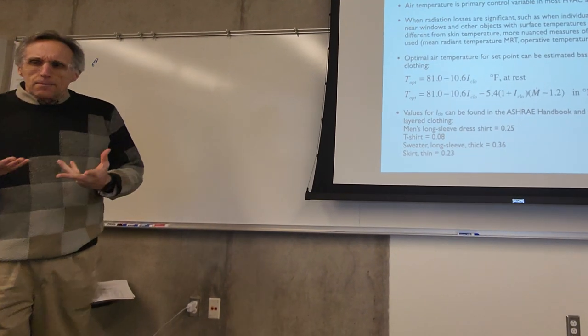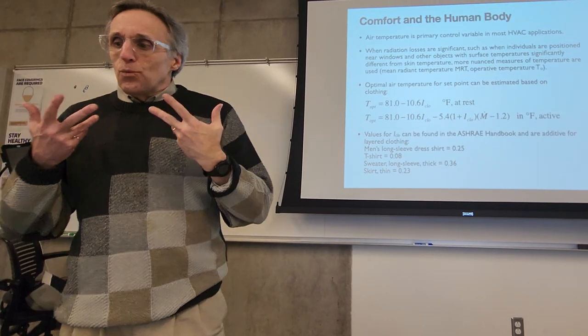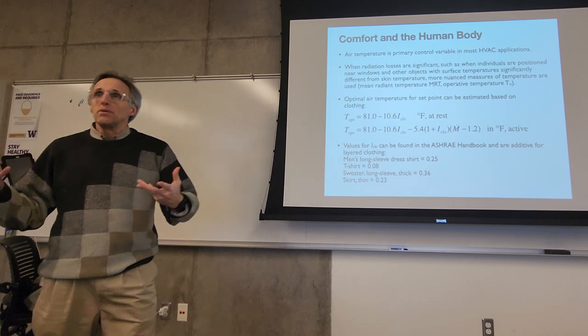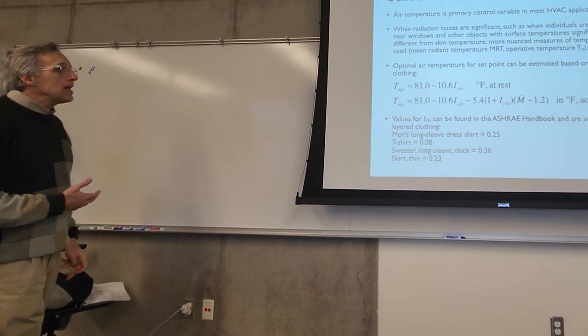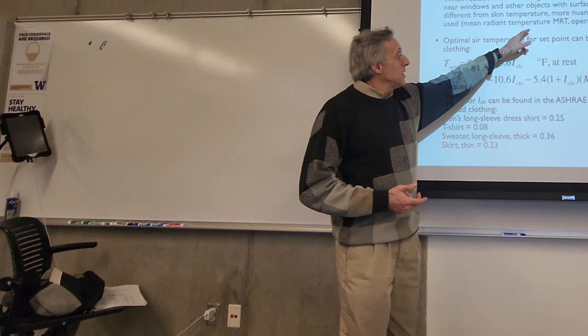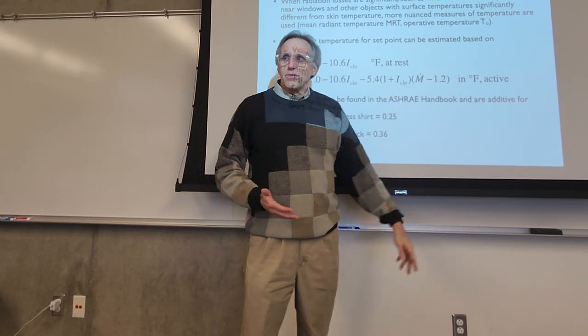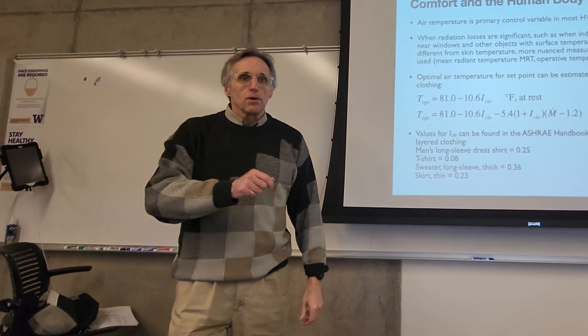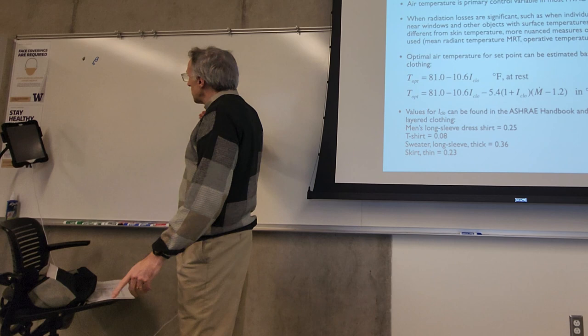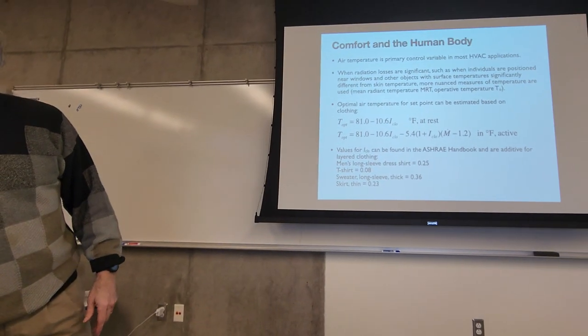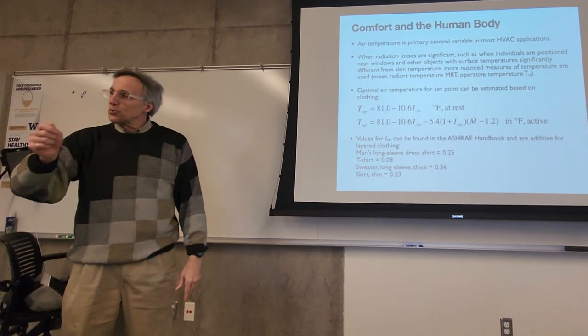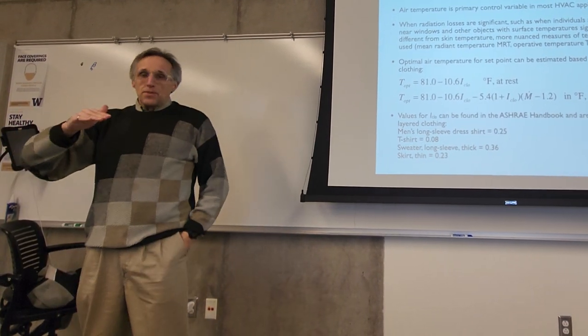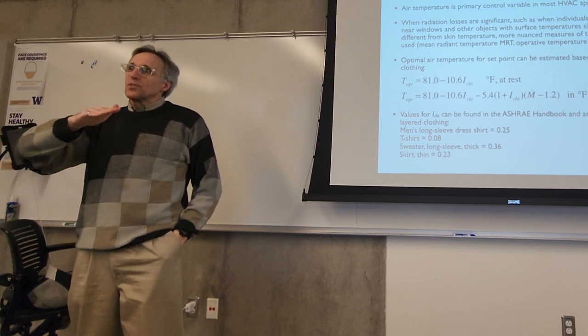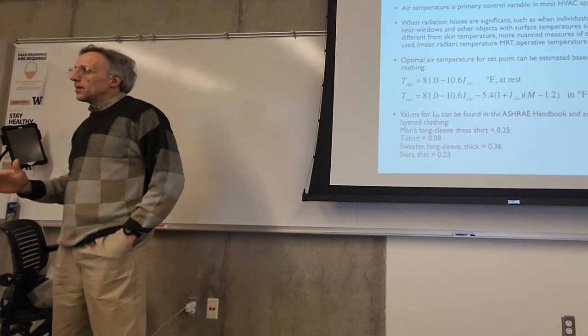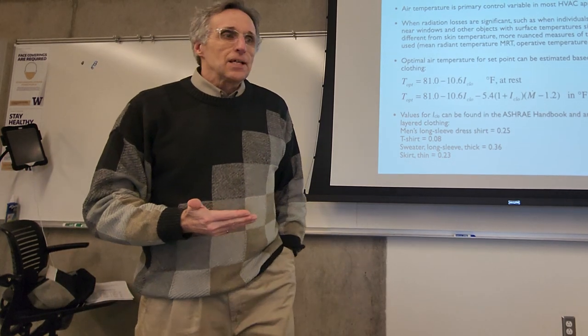components. Now, if we wanted to do a really exact analysis of the room environment, we wouldn't use the dry bulb temperature or the wet bulb temperature. We use something called the mean radiant temperature, or the MRT. It's really complicated. It's very hard to figure out. What you have to do is literally have a thermometer on every surface in the room. So you have a thermometer here, a thermometer on this podium, a thermometer on each desk. And what you do is you measure the temperature of all the surfaces and you multiply them by the area. So it's like a weighted average of the temperatures of all the surfaces in the room. And that would be the mean radiant temperature.